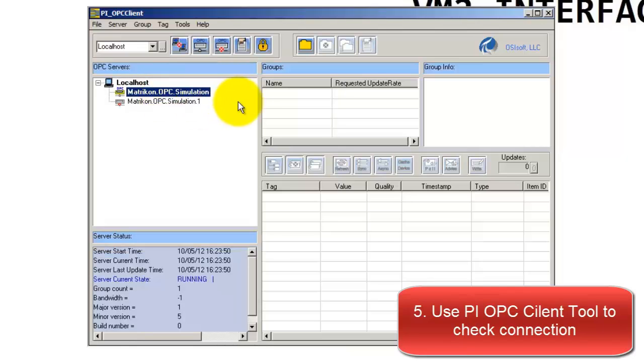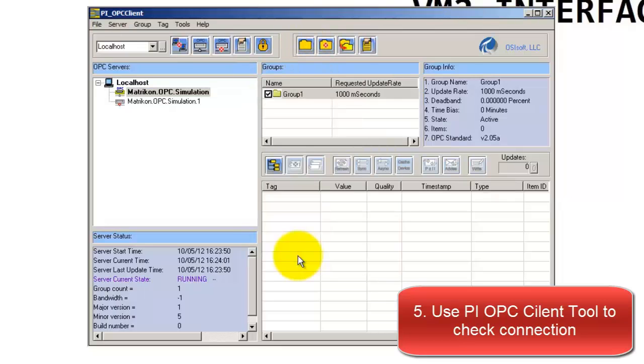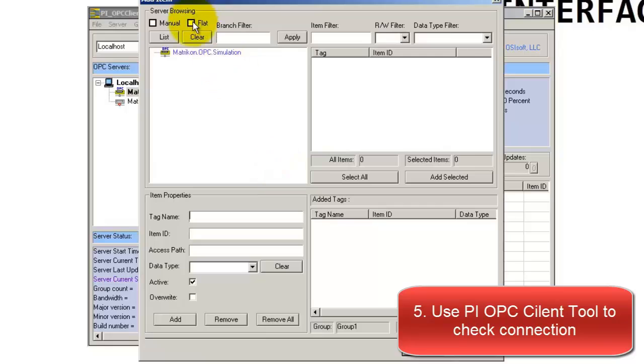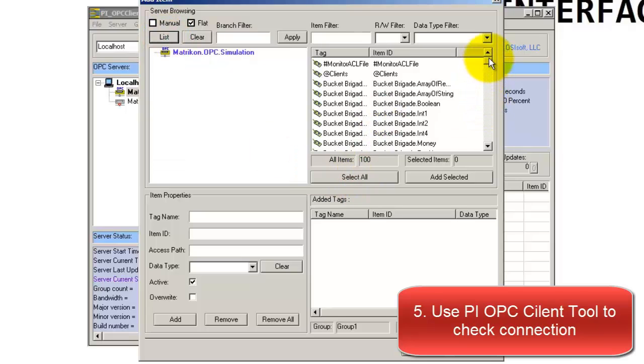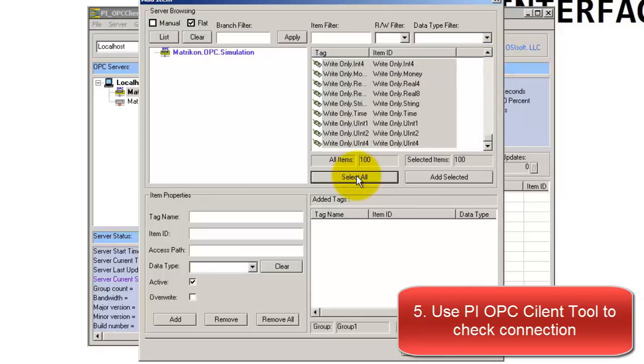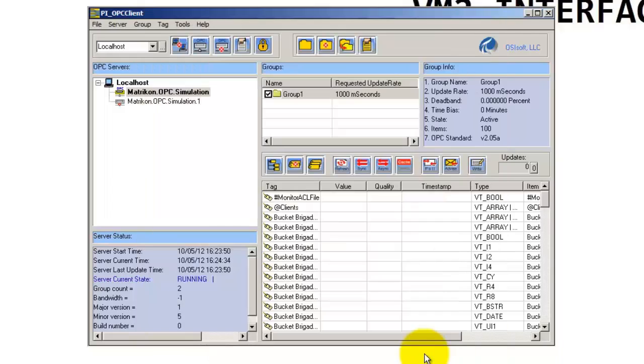We're going to be connecting to the Matrikon OPC Simulation server — just double-click to connect. Now that we're connected, we want to take a look at the values for different tags. Go to the yellow folder, which is Add Group, and hit Create. Then go to Browse OPC Server and Add Tag. From there, check the box for Flat and hit List. Then select All — these are all the tags we're getting from our OPC server. Select All, Add Selected, and hit OK.